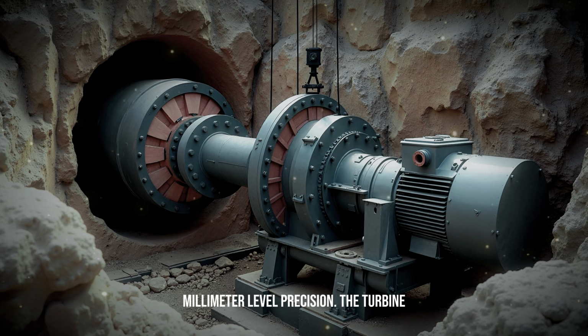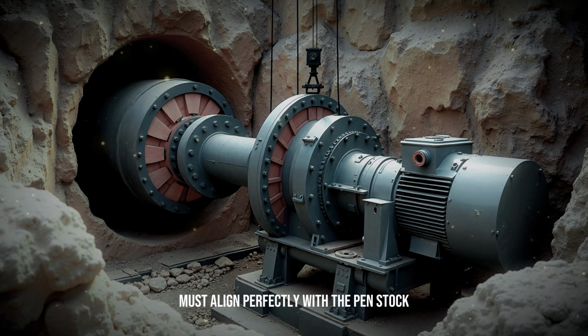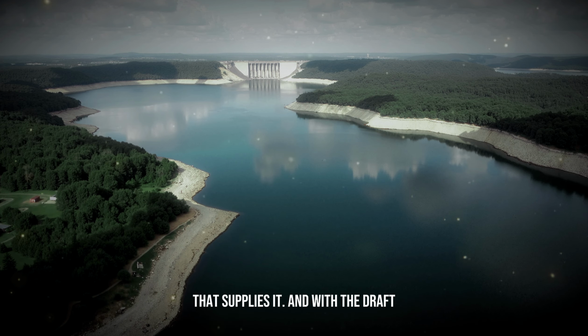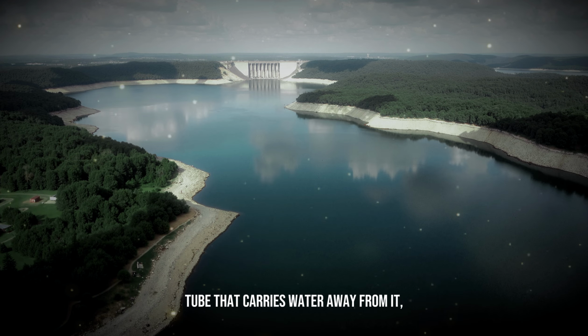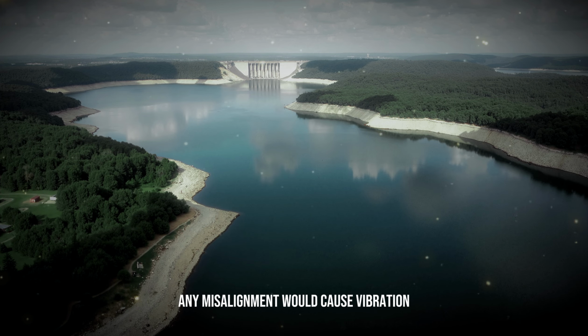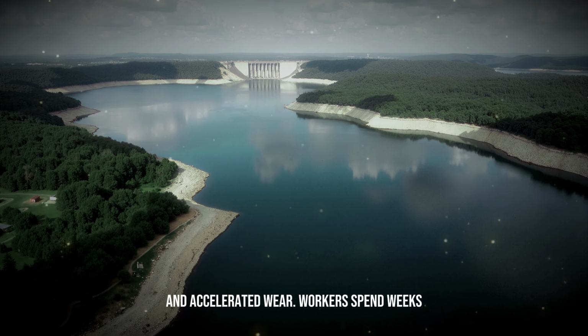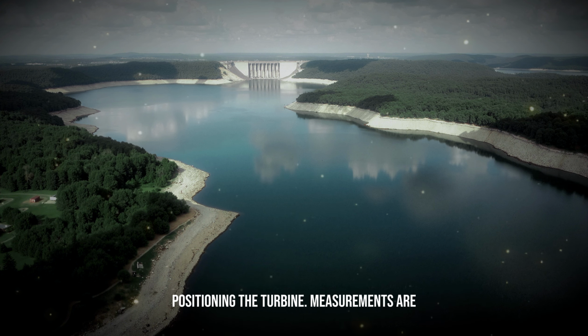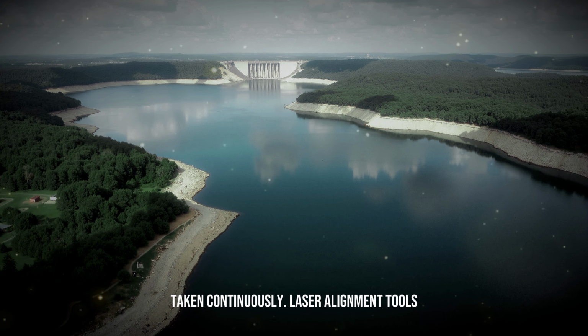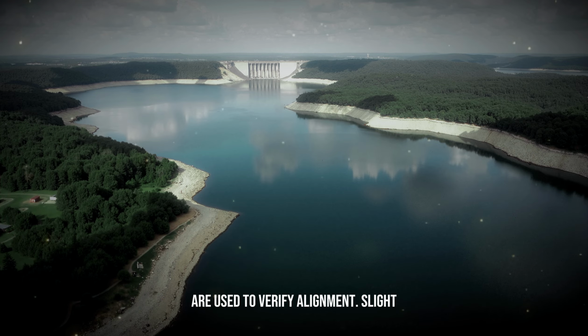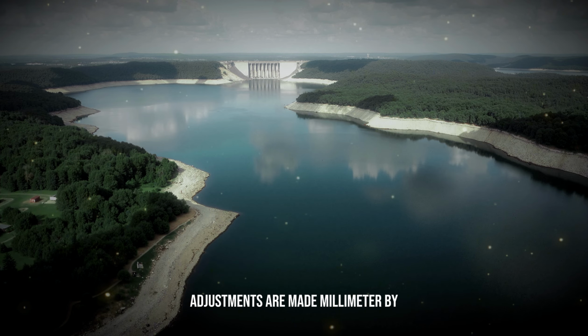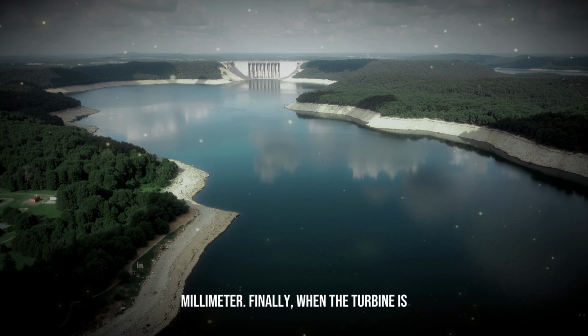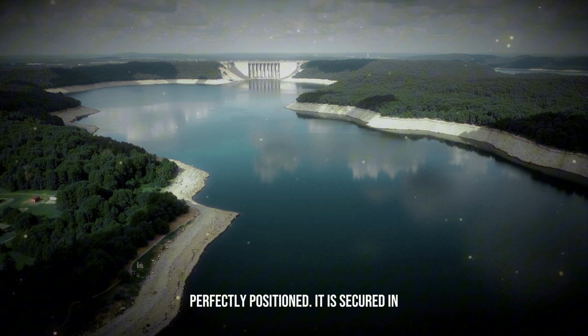Positioning requires millimeter-level precision. The turbine must align perfectly with the penstock that supplies it and with the draft tube that carries water away from it. Any misalignment would cause vibration and accelerated wear. Workers spend weeks positioning the turbine. Measurements are taken continuously. Laser alignment tools are used to verify alignment. Slight adjustments are made millimeter by millimeter. Finally, when the turbine is perfectly positioned, it is secured in its final location.